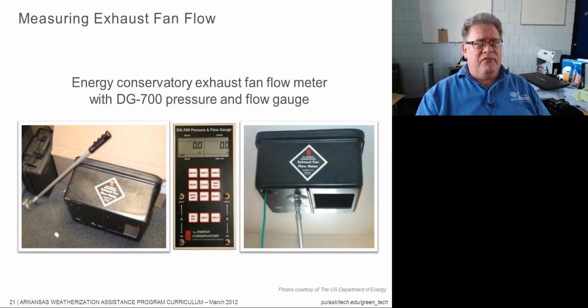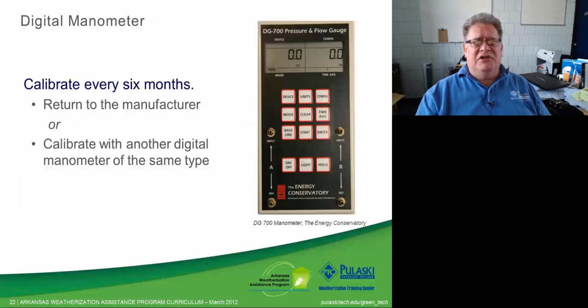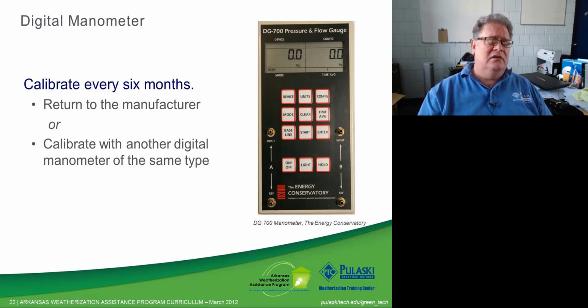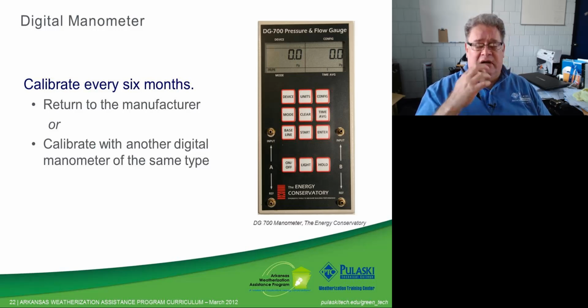Okay. Your digital manometer, again, should be calibrated about every 6 months. Return it to the manufacturer, or check it against another manometer of the same type. You can take this manometer and check it against another manometer. And if you go to the Energy Conservatory's website, they have some field calibration schematics and instructions on how to field calibrate these.